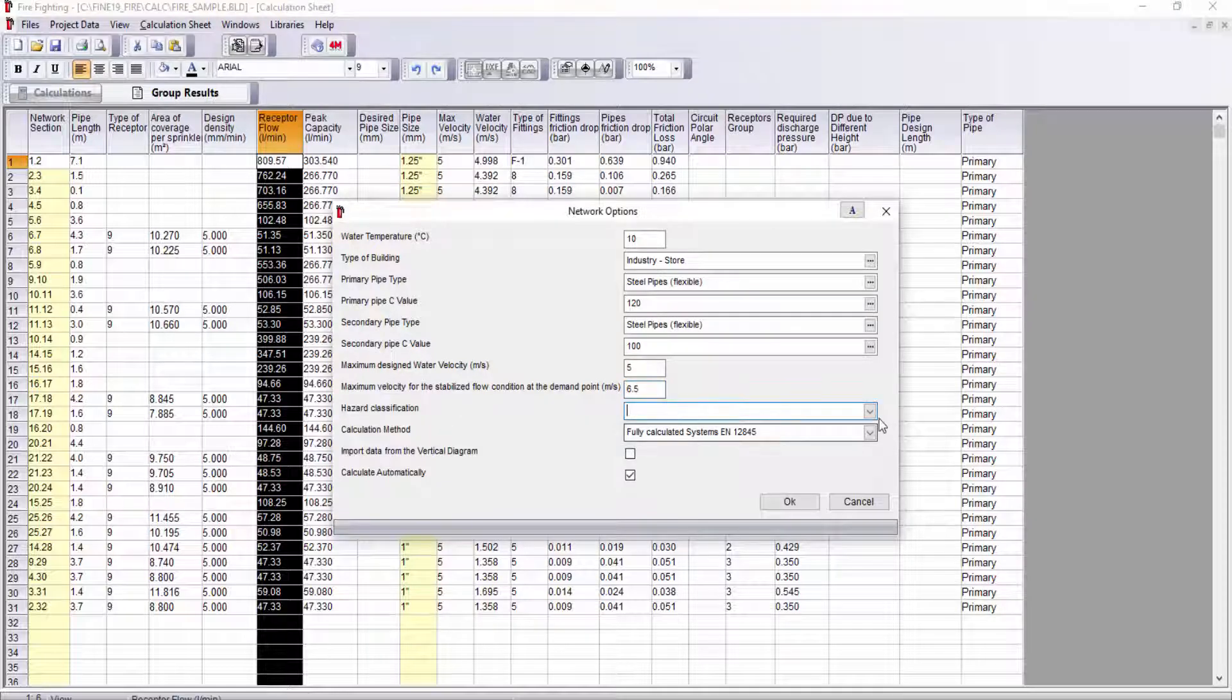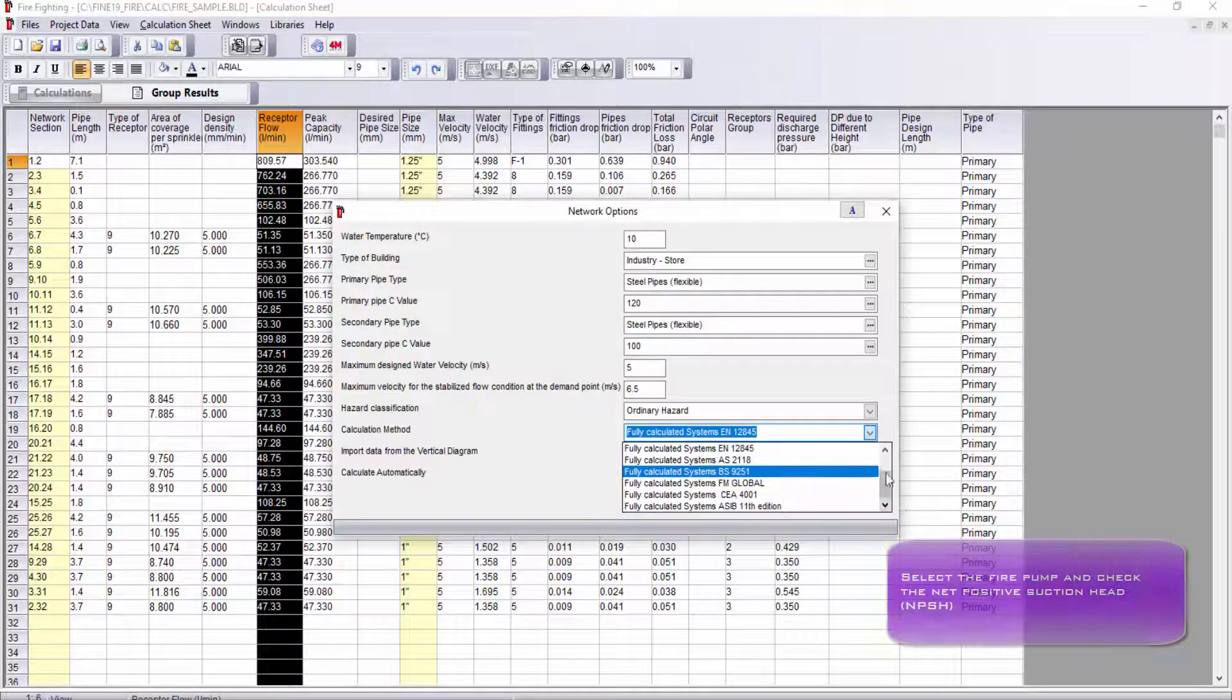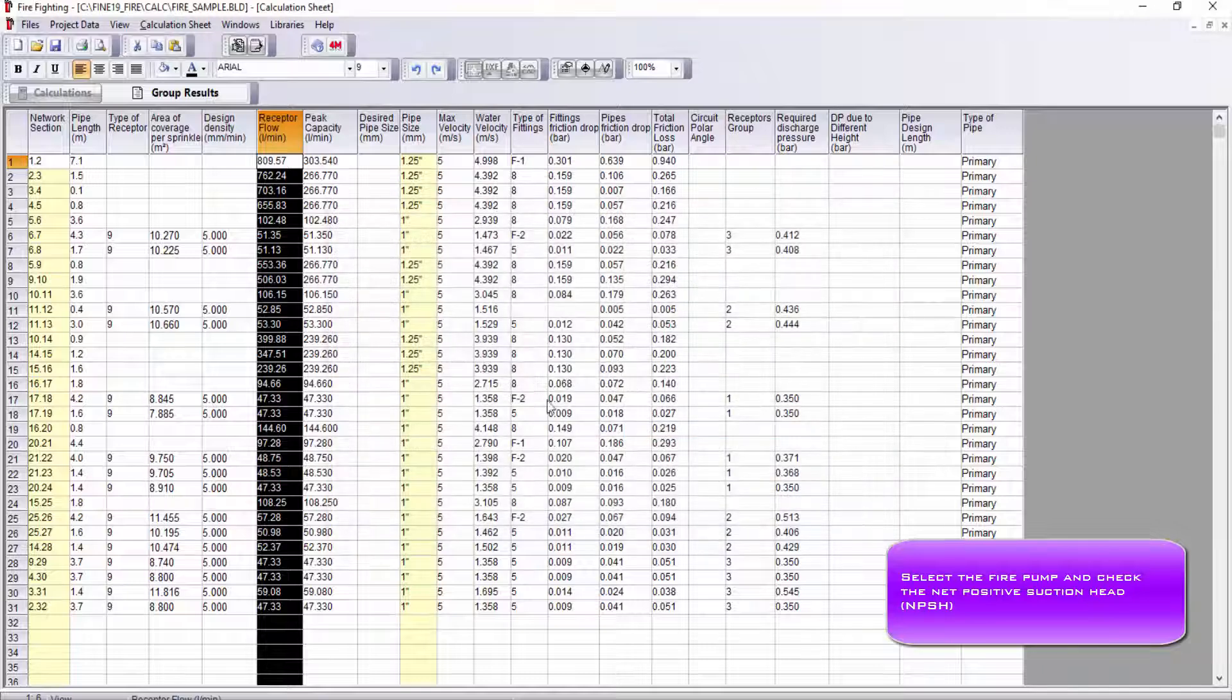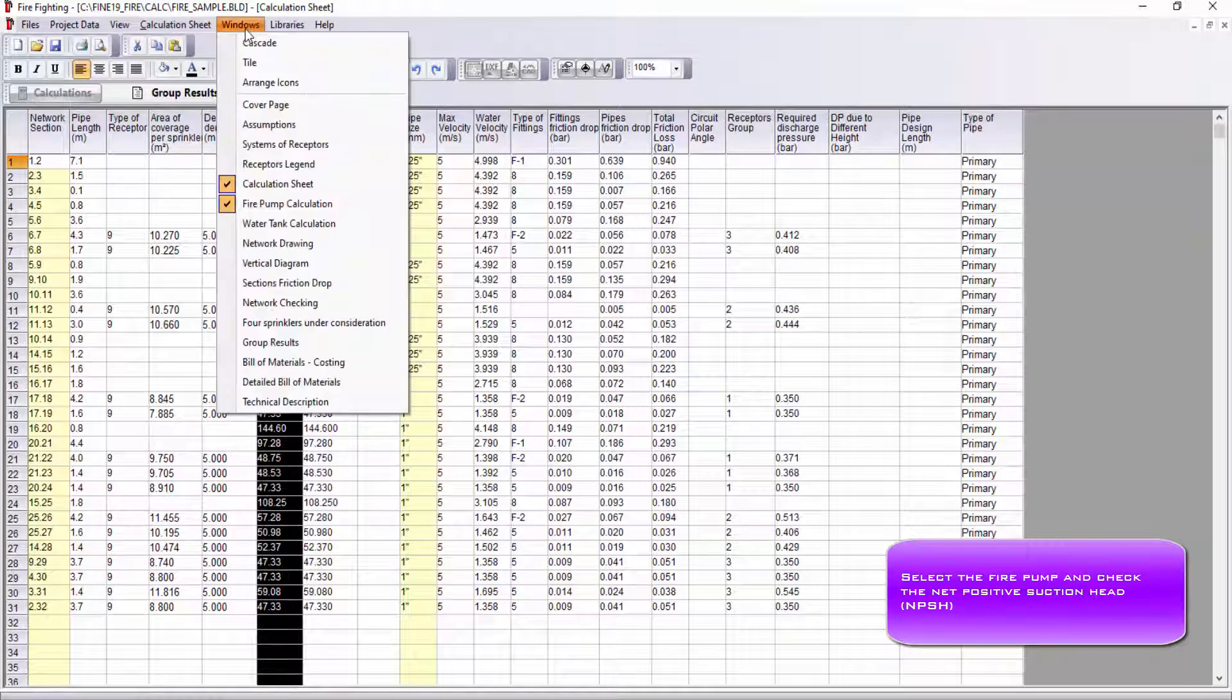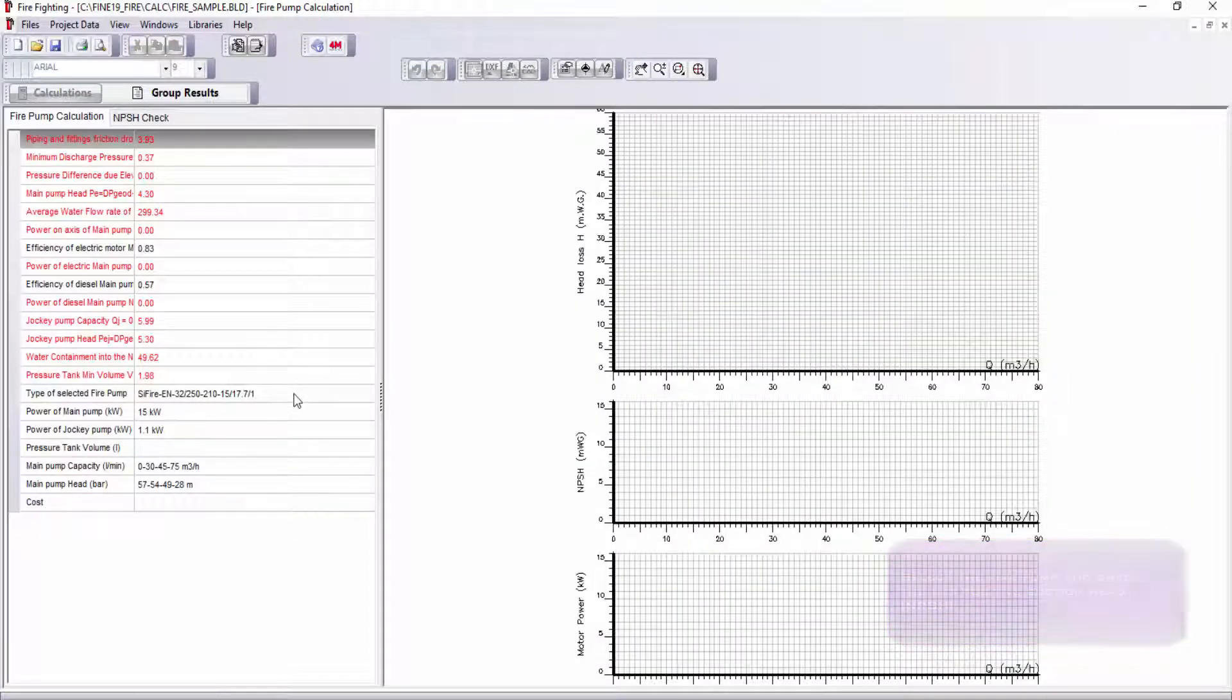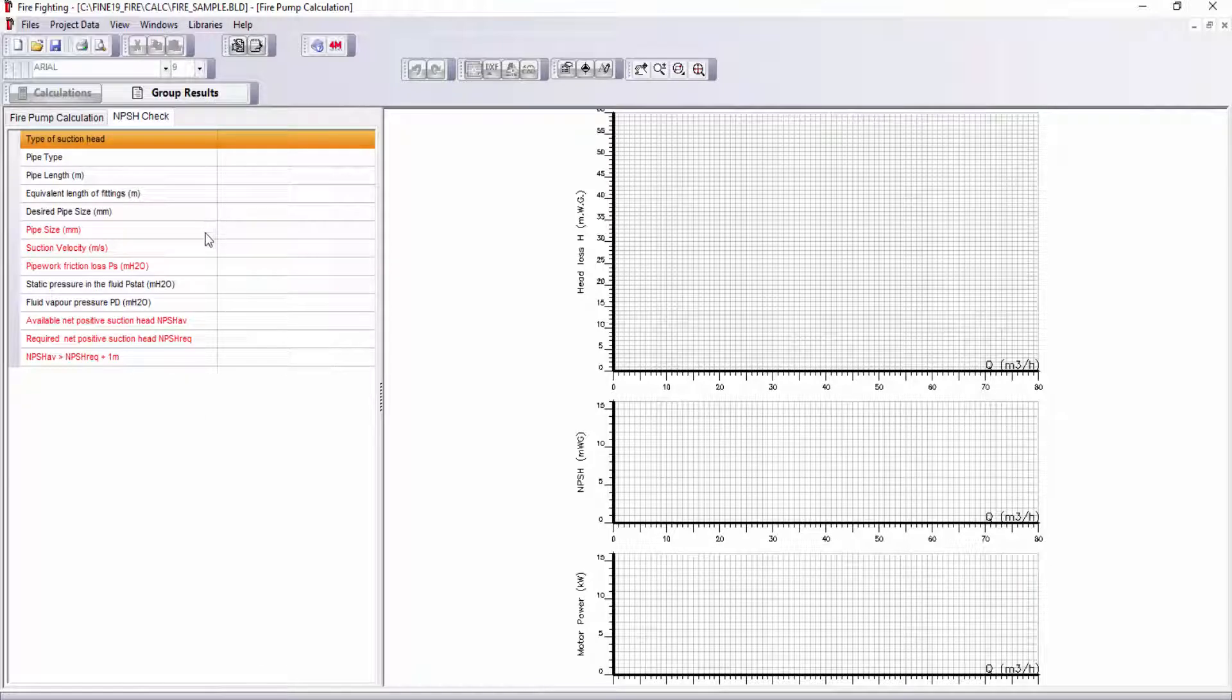In Windows Fire Pump Calculation, you can select the fire pump, calculate the motor power, and run an NPSH (Net Positive Suction Head) check. With red color, it appears the detailed calculation data of fire pump based on most favorable and most unfavorable groups.